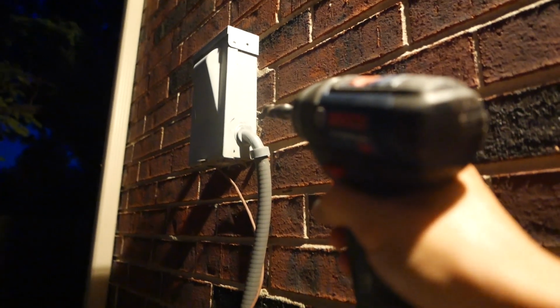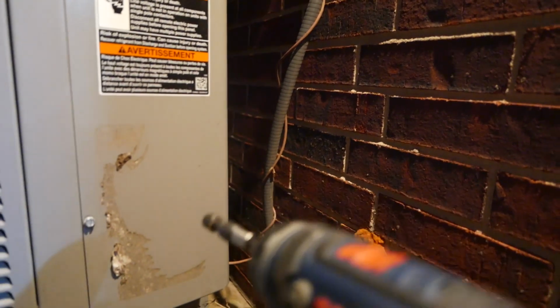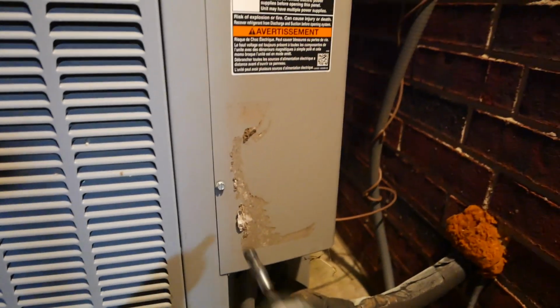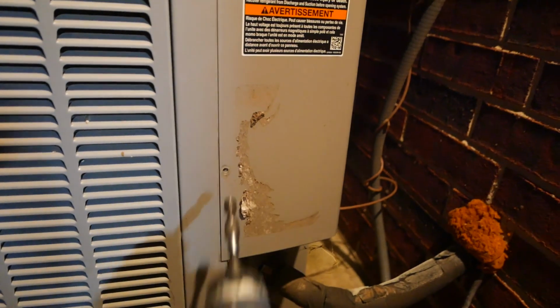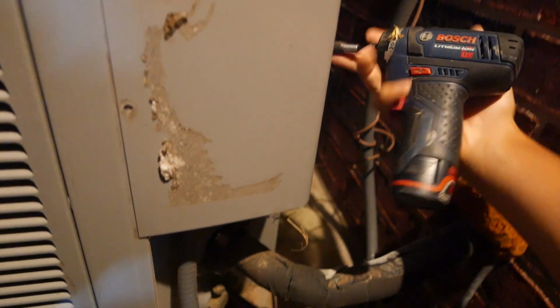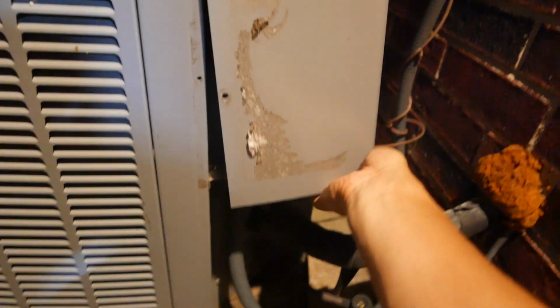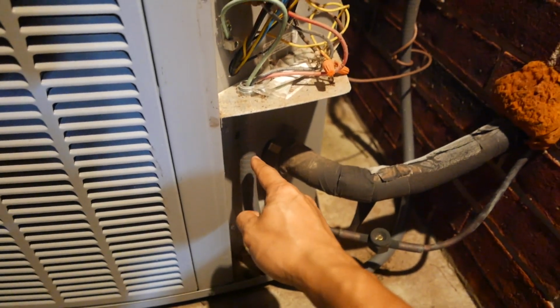So now I'm at the breaker and the breaker hasn't tripped. Alright, so the voltage from the shutoff goes all the way down into this panel right here. So this panel has two screws. Let's take it off real quick. Don't want to lose those screws. Alright. If I take it off, what you can see here is the voltage coming up, and alright, this is a lot better.